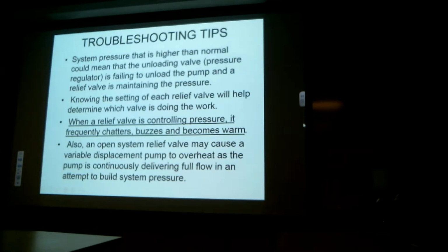So pressure higher than normal, what I suspect is that whatever is controlling system pressure has failed. If you've got an unloading valve and a relief valve and the pressure is higher than normal, the system relief valve is controlling pressure. Knowing that, there is some indication also that the unloading valve may have failed.